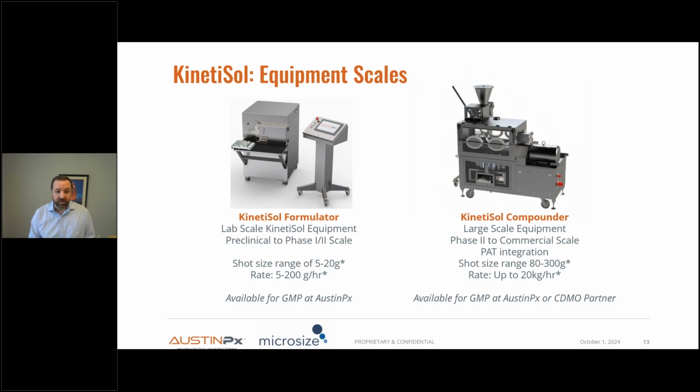And then there's the KinetiSol compounder. It's our larger scale equipment. It's got geometric similarity to the formulator. However, we don't need a third step to go from a phase 2 to a commercial scale. We can do that all with this machine, and it's got PAT fully integrated. The shot size is about 80 to 300 grams versus the formulator, and the production rates are up to 20 kilograms an hour.